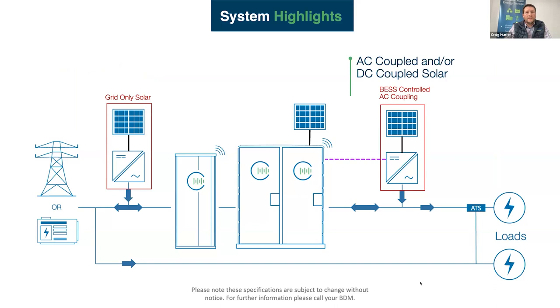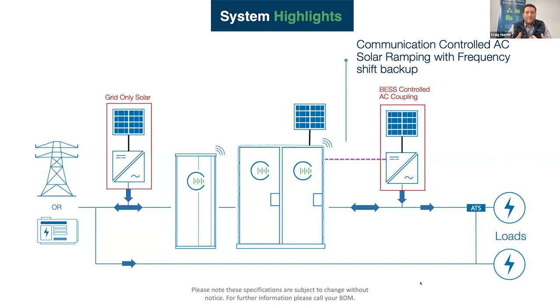You can use AC or DC coupled PV. For people who don't understand the difference, one's connected on the AC bus, one's connected on the DC bus. With AC coupled PV connected to the load output side of this product, it can be controlled via frequency control or frequency ramping in an off-grid or islanded situation where the grid may fail, so the PV can remain connected when the grid has failed.